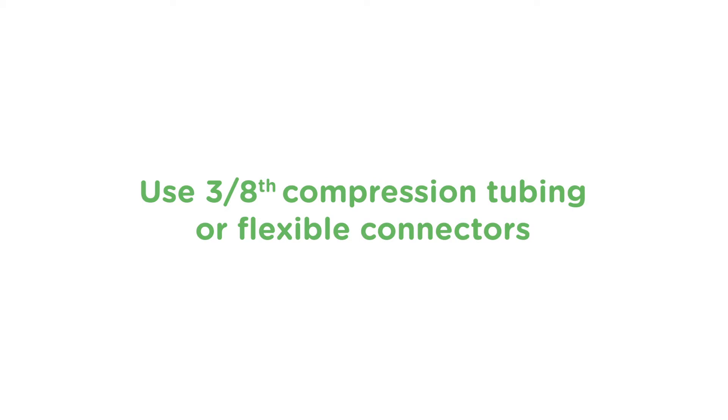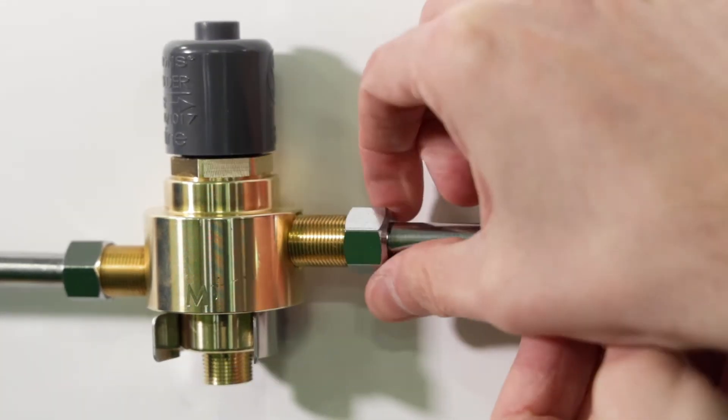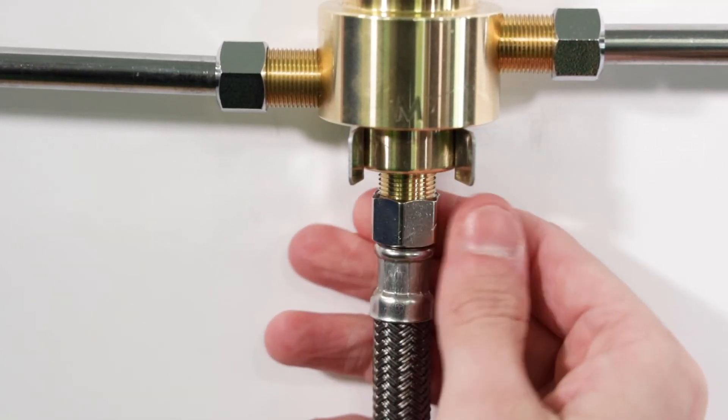Using 3/8 compression tubing or flexible connectors, connect the hot water to the hot inlet and the cold water to the cold inlet, and then connect the tempered water outlet to the single supply line of the faucet.